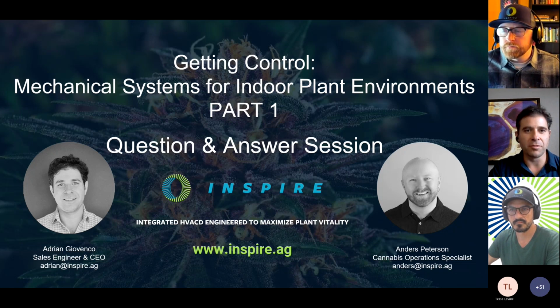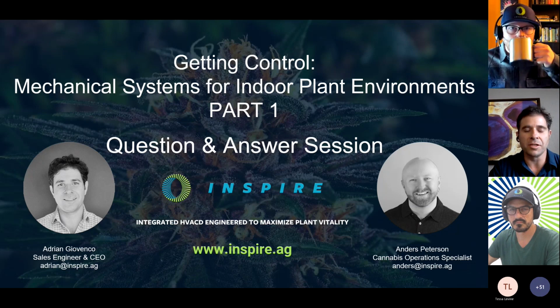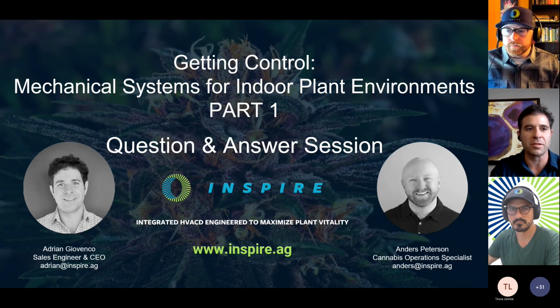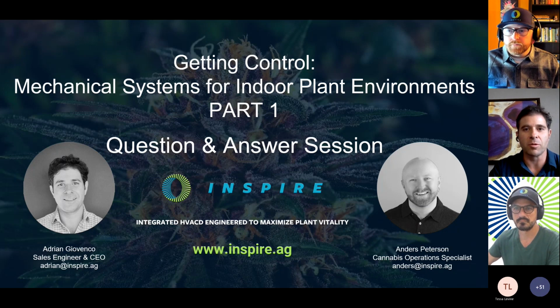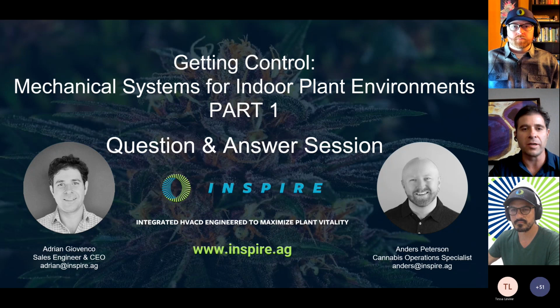Yeah, I think you really nailed it there, Anders. It's a wide range, and it's really understanding what redundancy means for a particular cultivator or cultivation business. Most importantly, start there, and understand what the budget requirements or restrictions might be. I think the overall system size and scale offers the ability to, in many ways, more inexpensively include additional points of redundancy than on a smaller scale, or with a hydronic type system, as an example, compared to individual DX type units, packaged units, or split systems.